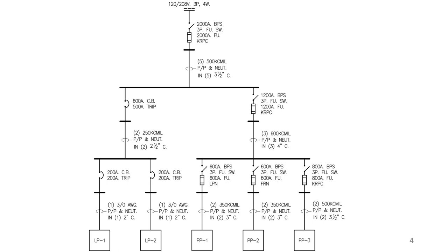And for example, if I'm looking at this one line, I've got a 2000 amp fuse. And a lot of people are asking, what should I use, a breaker or a fuse? And in my experience, I learned that you have to look at what is the available fault current. If you're looking at a low available fault current, of course, a circuit breaker is going to be cheaper.